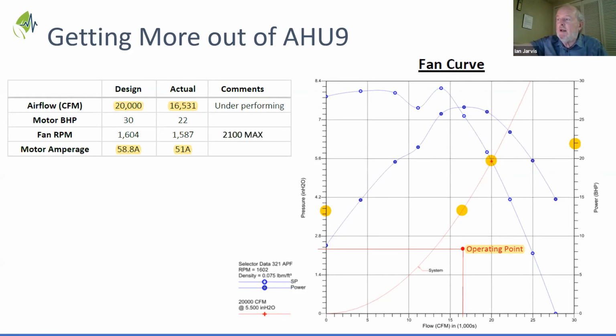You see the red line there of the system curve, and you see the yellow dot at about 5.6 inches of static and 20,000 CFM. And you can see that that's what the system should be running at. What, again, over time, everybody will get familiar with is that nothing on this chart makes sense, and it needs further investigation, exactly as Simba was saying, so that you know what you're looking for.